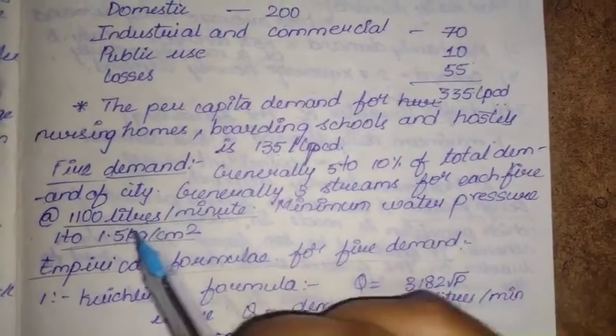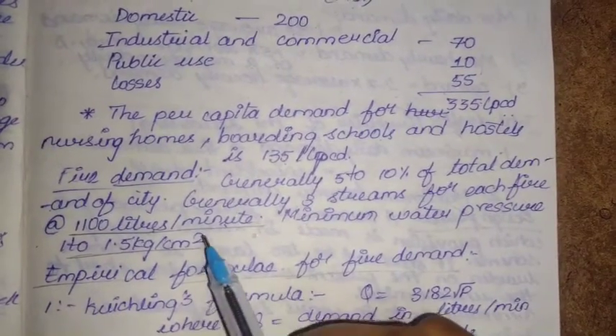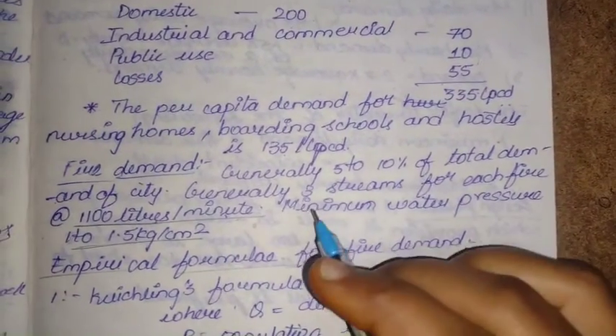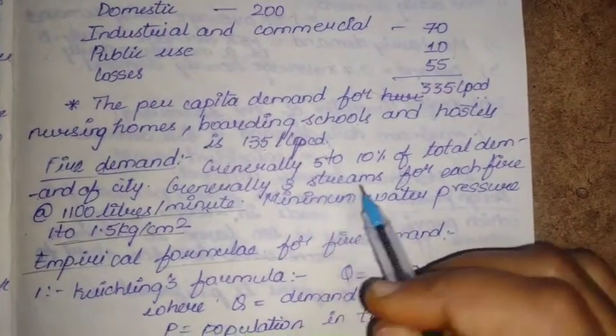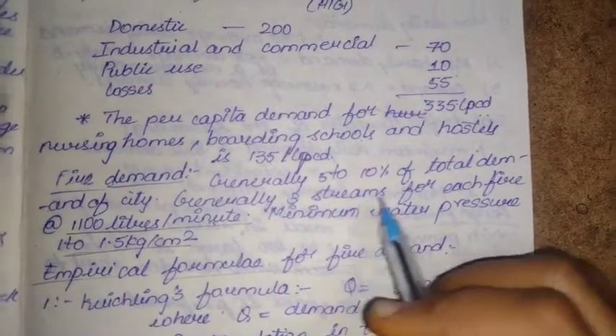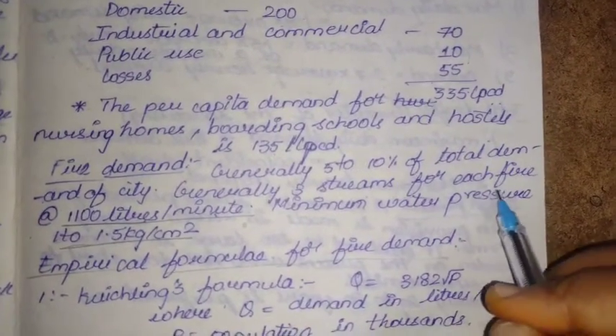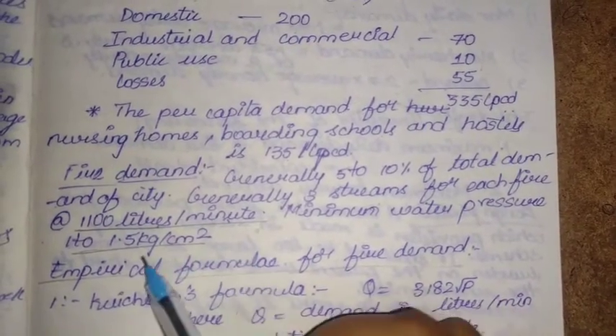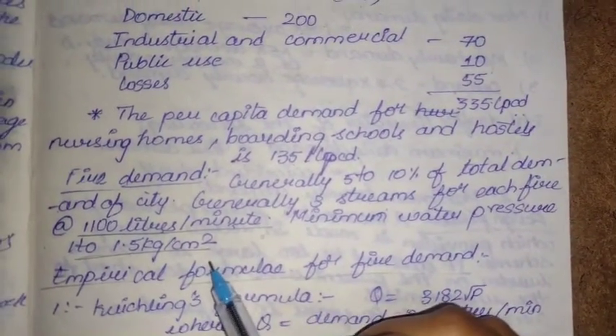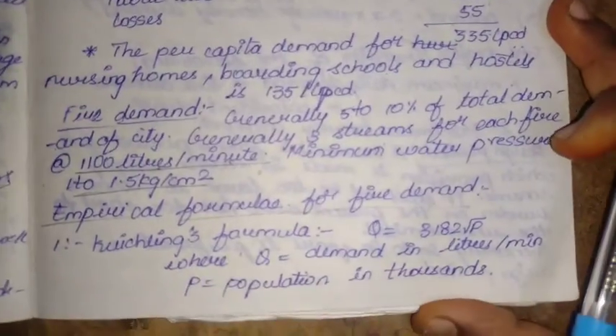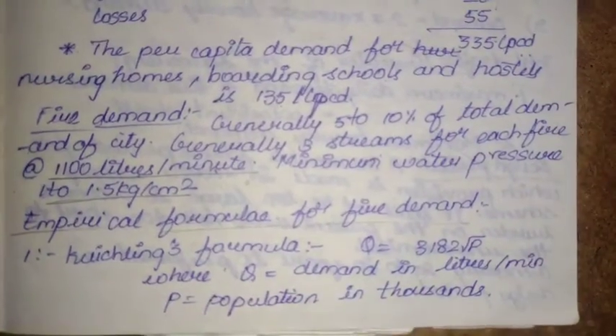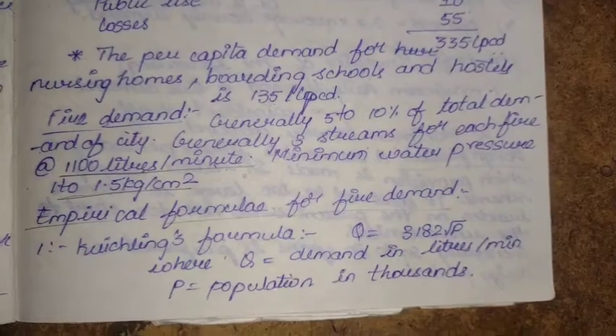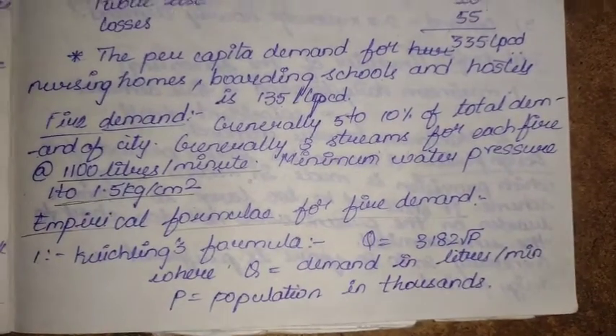Generally, three streams per fire at 1100 liters per minute are considered. The minimum water pressure to be maintained is 1 to 1.5 kg per centimeter square. Now coming to the empirical formulae for fire demand, the first one is the Kuichling formula: Q = 3182 × √P.